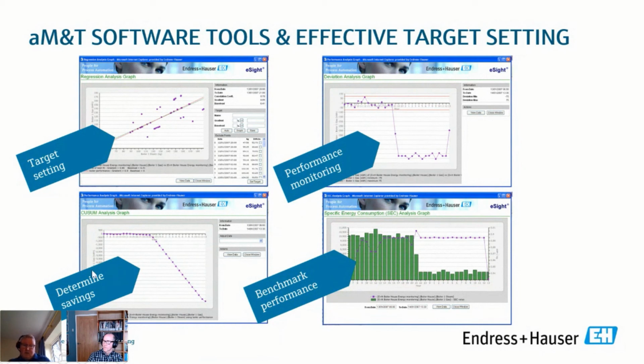So here we've got another analysis tool called a CUSUM—this is the cumulative sum of these deviations. If we look at all the deviations and sum them, we end up with a straight line. This is a great condition monitor, because as soon as something's changing, whether it's heat exchanger fouling or something else, and it's changing very slowly, it's going to be very hard to pick up through gas bills and things like that, but we'll pick it up with a CUSUM.